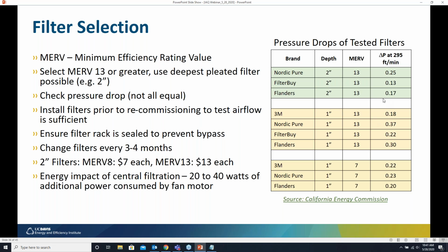And then the situation can get even better if you look at 2-inch deep filters, you can get even lower pressure drops. So really consider MERV 13 filters. They should work in almost any application. Obtain the pressure drop, look at the pressure drop of the filters you're buying, and compare it to the filters you have currently. You might be surprised.